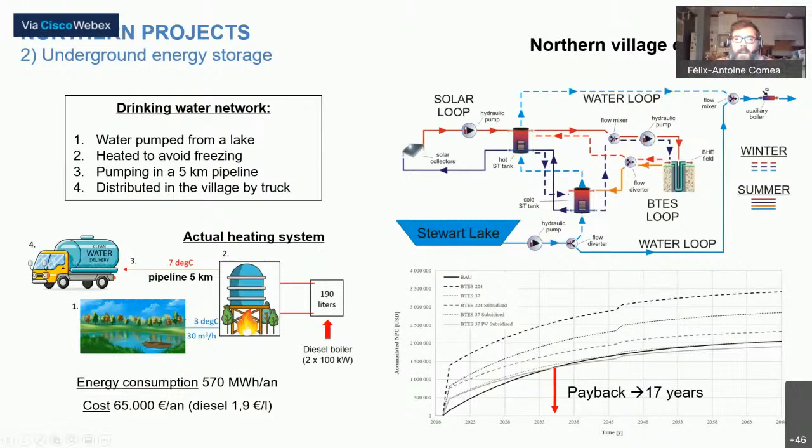More precisely, we design a system for the drinking water. They are using water from a lake that is 5 kilometers far from the village. Presently they have to pump it to put it in the reservoir and heat the water to avoid the freezing during the transport. Then the idea is to build an underground system to replace the heating from furnaces and diesel and to do it entirely with geothermal energy.